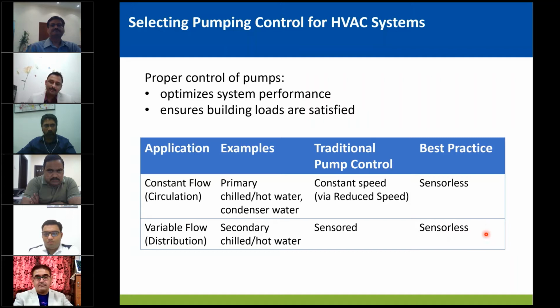You can also change set points very easily from the smart pump interfaces. So you don't have technicians or operators forgetting the location of the sensor in a large building. When the operator is changed, often this information is not passed on, and we have seen cases where the operator doesn't know where the sensor is placed. So these kinds of issues can be taken out, and best practice could be sensorless control practice.